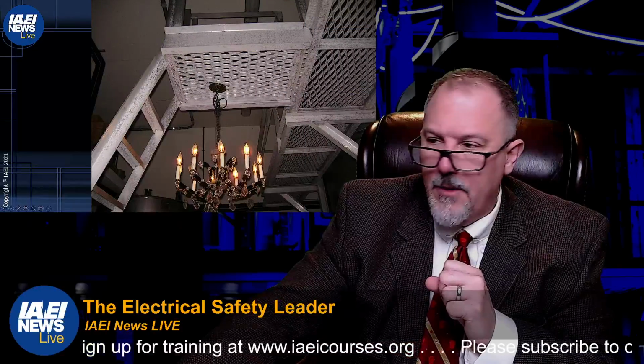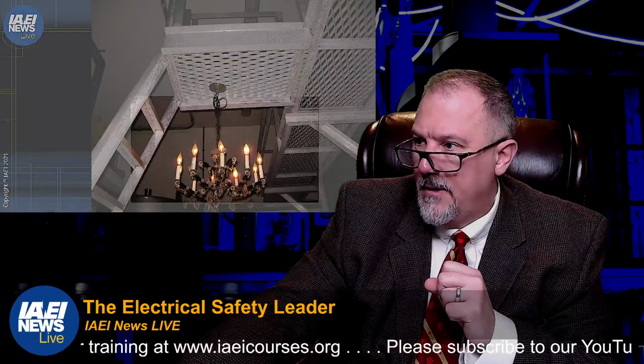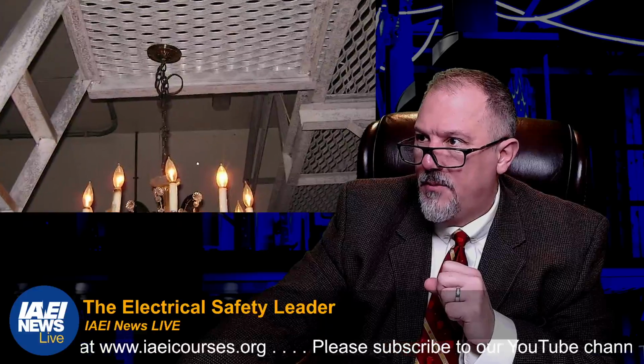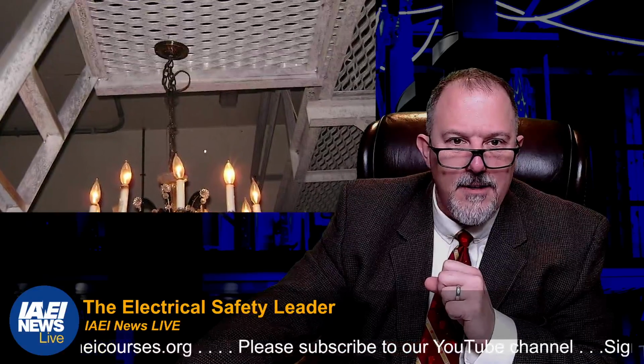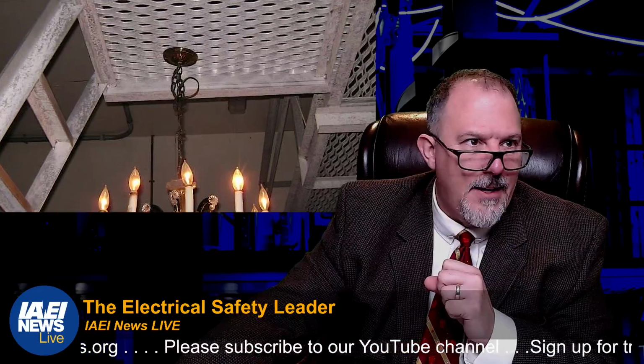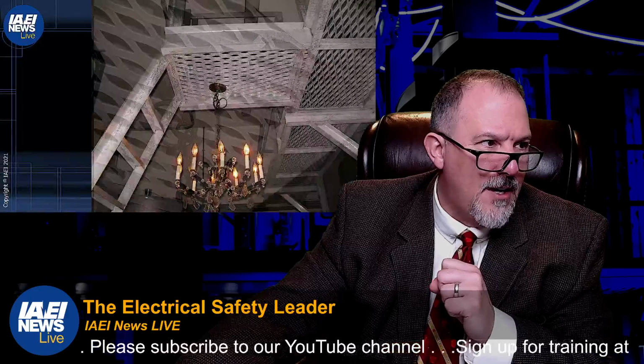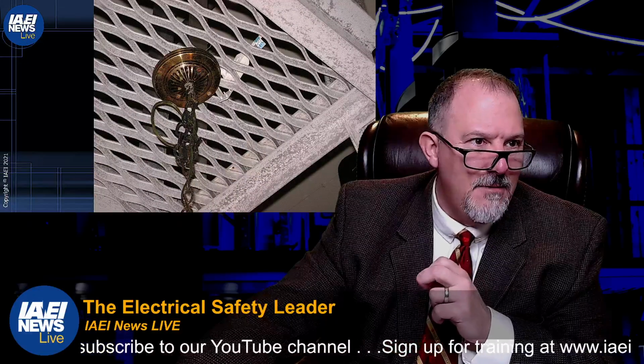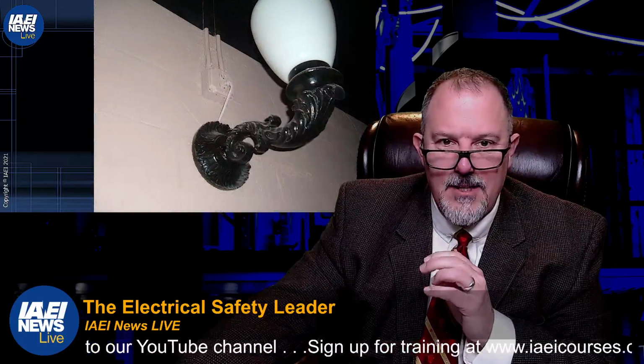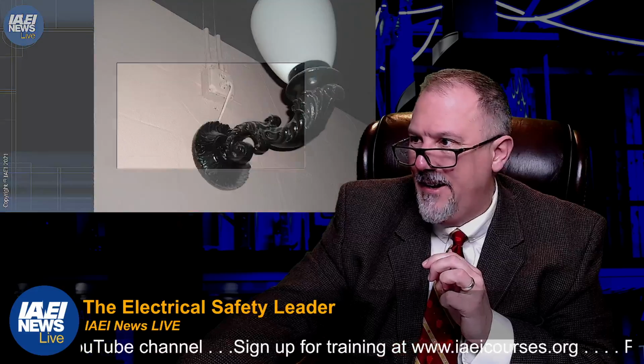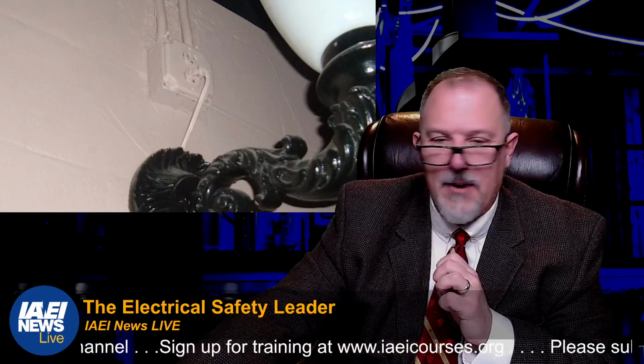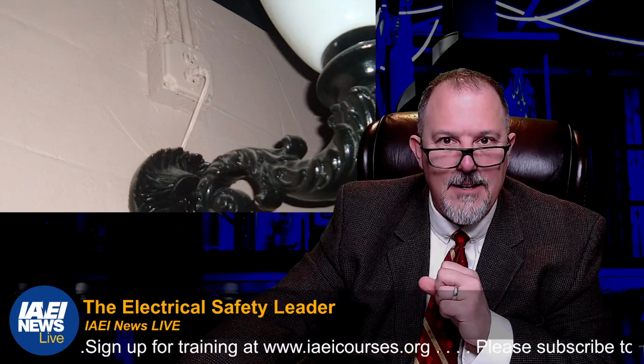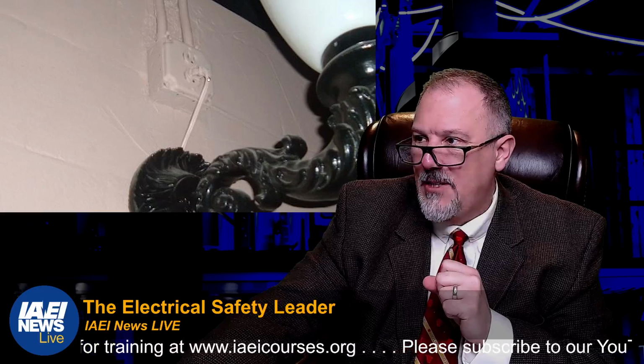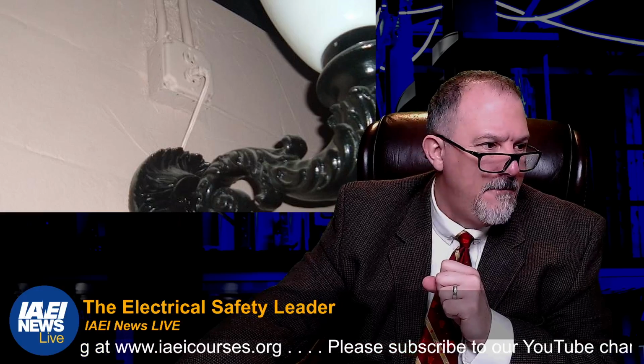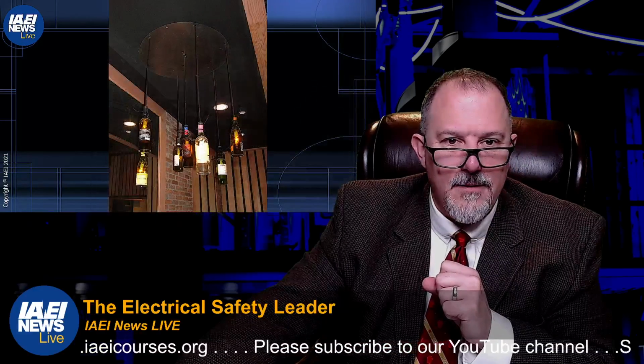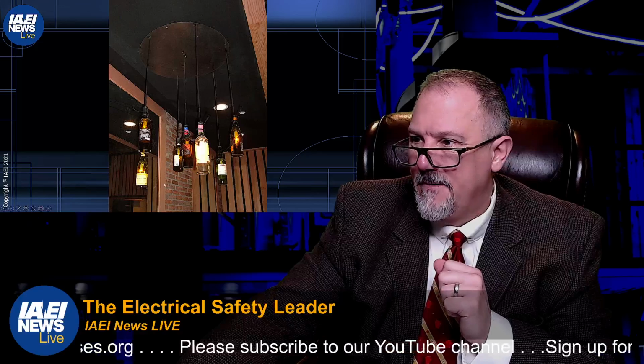Now, I'm not sure about this one. I mean, who would put a chandelier in that location? But, you know, I don't know. Proper use, you have to make sure it's listed for the application. Look at this one. Well, is that a proper application? I think not. That SPT-2 cord doesn't look good. How about this one?